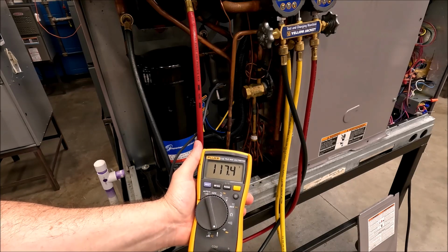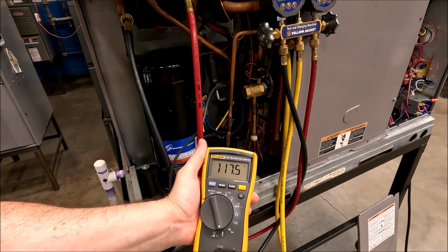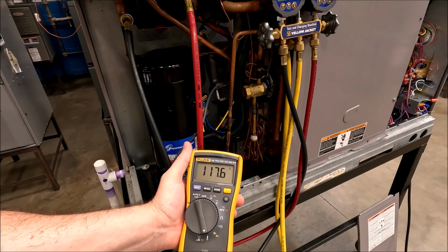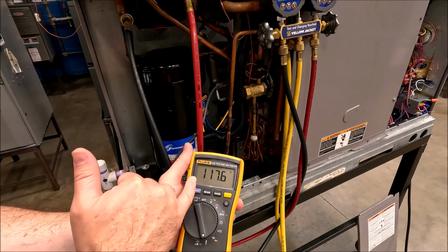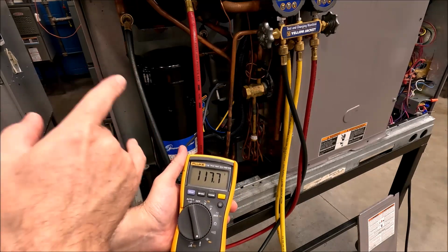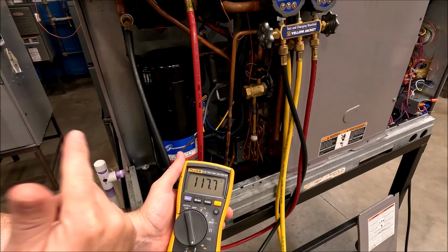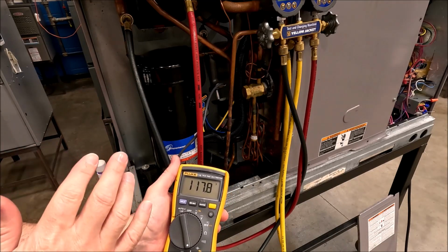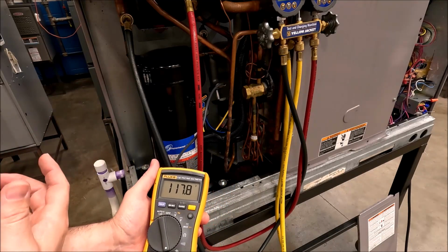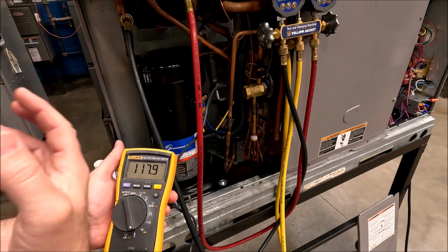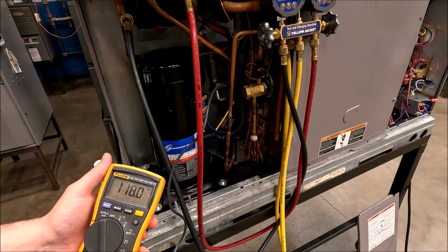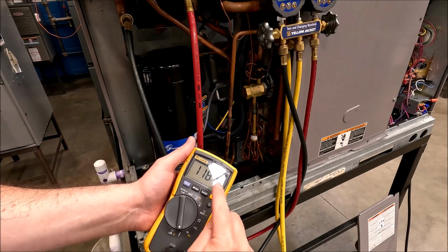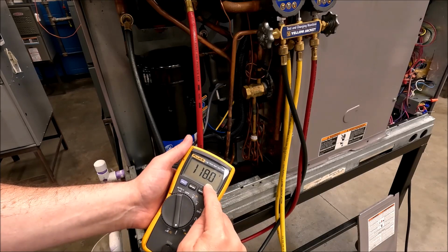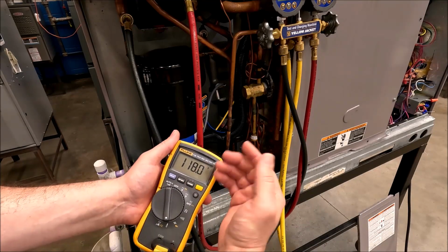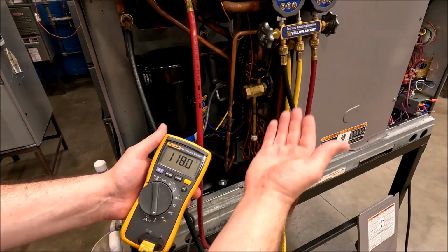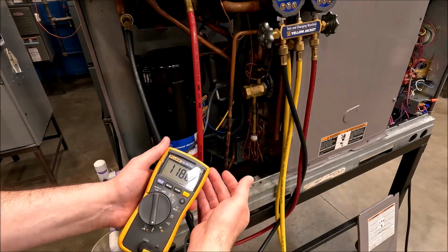Subcooling is not an increase in temperature, it's a decrease in temperature. We're cooling it, we're taking the heat out. So you have to realize that that discharge line is a high temperature, high pressure vapor. The whole job of the condenser is to reject that heat from the evaporator and the heat of compression in that compressor and get rid of it. So that 118, we're not just gonna do the big number, subtract the small number, because we wind up with almost 40 degrees of superheat.